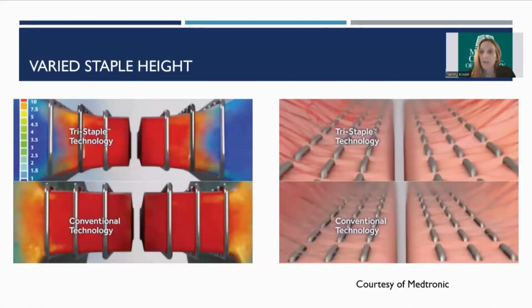This is technology advancement courtesy of Medtronic. Medtronic is looking at varied staple height, and it's designed as a stepped cartridge face. Again, per the manufacturer, they believe that this delivers graduated compression. You can see how this happens in a graduated rather than a more standard fashion across the 3 rows of staples. And they believe that helps generate less stress on tissue during compression and clamping.